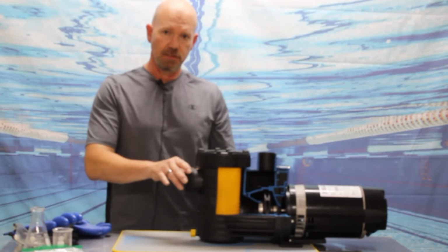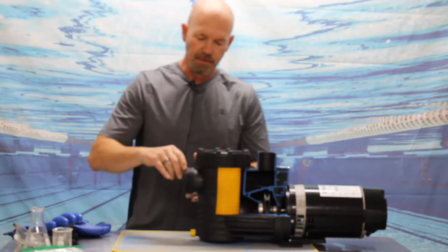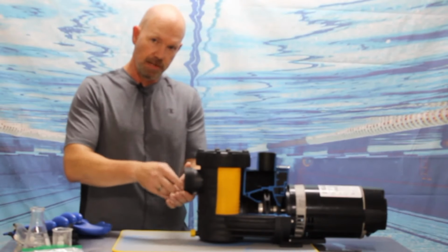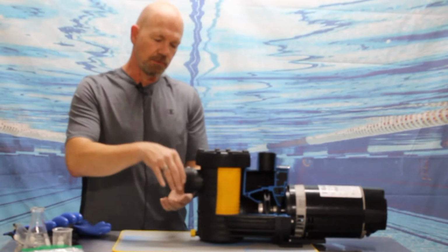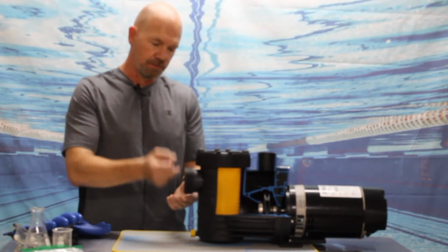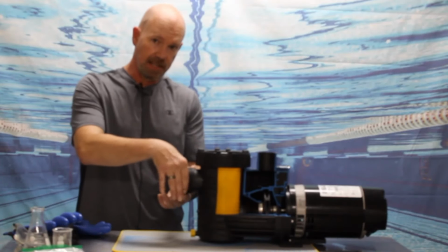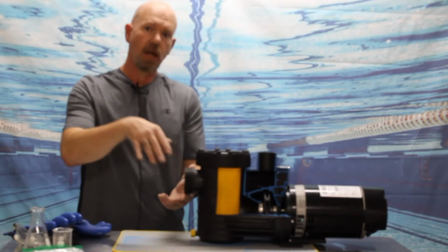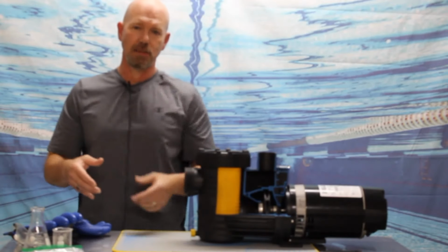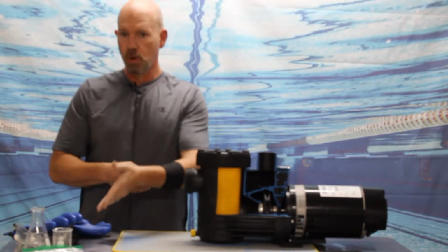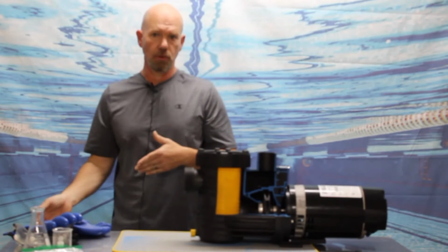Now, some folks like to use soapy water. I like to use shaving cream. With the pump running, if you spray the shaving cream completely around the joint, I like to start with this one right at the face of the pump first. If I'm drawing in air from that point, you'll see a very notable funnel right in the shaving cream itself. If I don't see any indication of a suction leak here, I'll go to the next joint, to the next joint, to the next joint until I find the place that I'm drawing in air or I hit the ground.